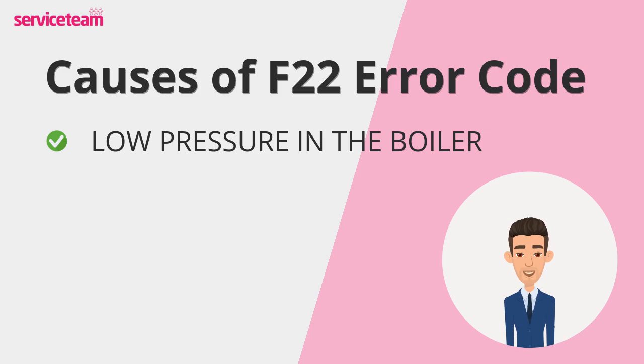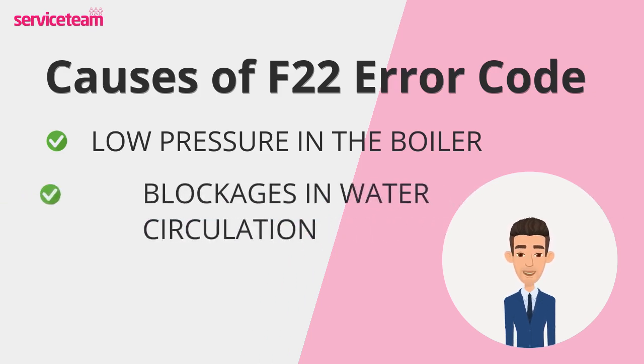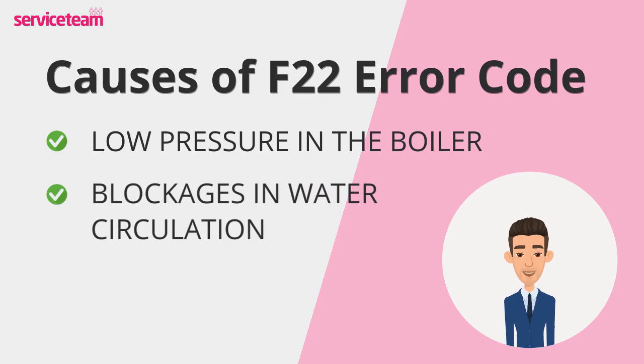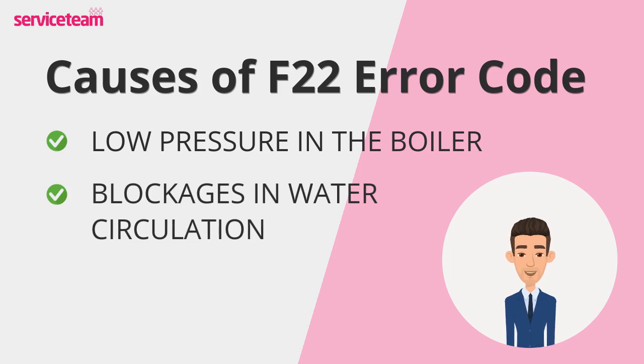This might be due to a leak, an issue with the pressure release valve, or simply the need to top up the water in the system. Another cause of the F22 fault is blockages in the system. Debris, sludge, or limescale can build up in the pipes, reducing water flow. When the boiler detects insufficient water movement, it triggers the F22 fault code.